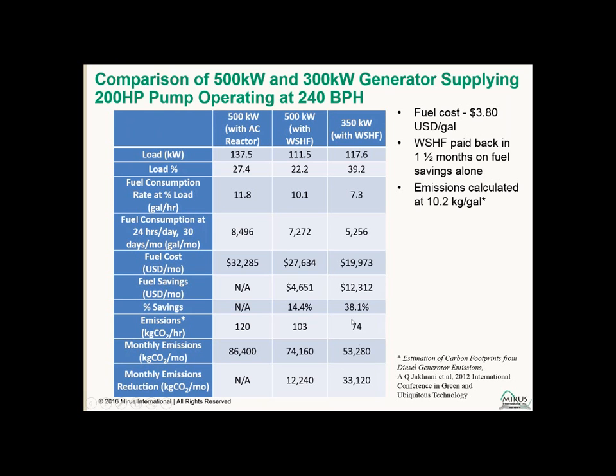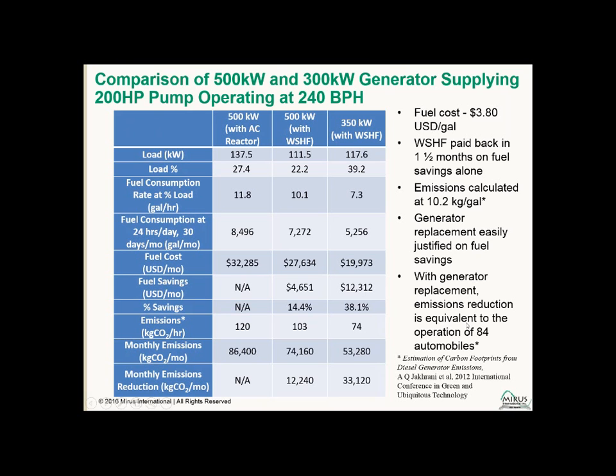And the emissions now were reduced by 33,000 kilograms of CO2 per month. The generator was easily justified on this reduction in fuel savings, and also the emission reduction proved to be the equivalent of taking 84 automobiles off the streets. So very easy to quantify, excellent fuel savings and emission reductions as a result of the harmonic mitigation.